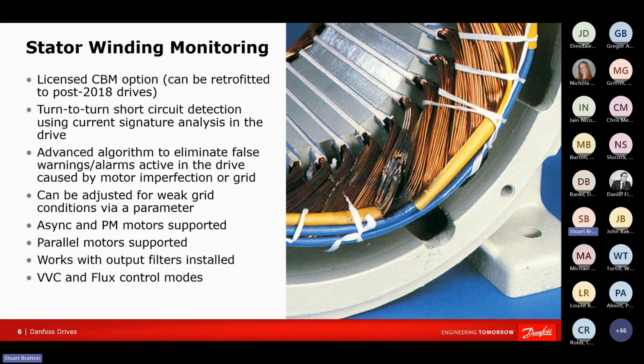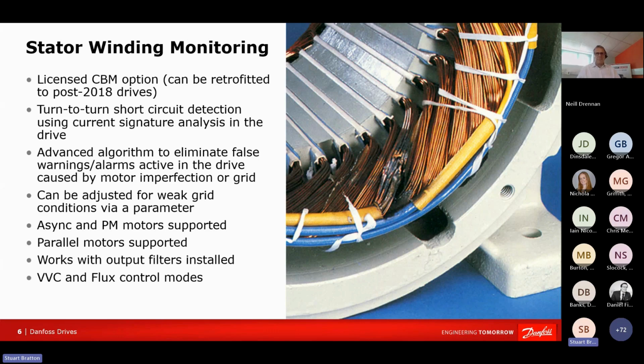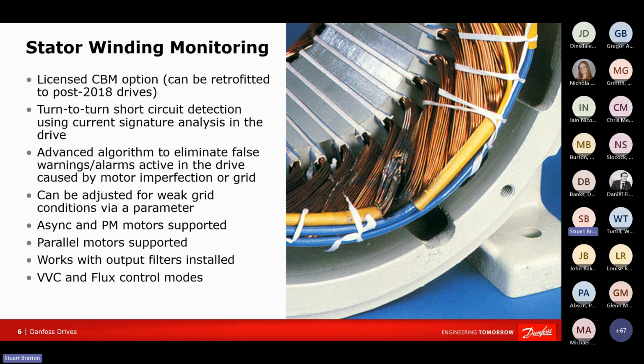That's now giving you plenty of time to get a spare motor in place if you haven't got one already. There are parameters to adjust the algorithm to account for the effects of a weak supply to the drive. We very rarely touch those, and this technology works with every sort of motor type that you can think of, really. Even if you've got a drive that's powering multiple motors in parallel.